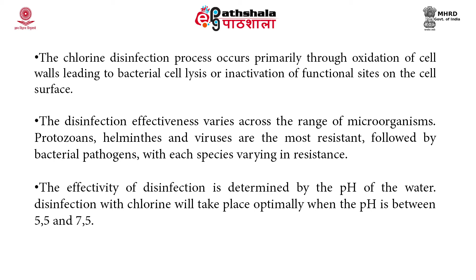The effectivity of disinfection is determined by the pH of the water. Disinfection with chlorine will take place optimally when the pH is between 5.5 to 7.5. The hypochlorous acid at this pH reacts faster than hypochlorite ions, and it is 80 to 100 times more effective. The level of hypochlorous acid will decrease when the pH value is higher. With a pH value of 6, the level of hypochlorous acid is 80%, whereas the concentration of hypochlorite ion is 20%. And as the pH value further increases to 8, this is the other way round. So, chlorine is very effective against enteric bacteria, but it is less effective against other bacterial species.